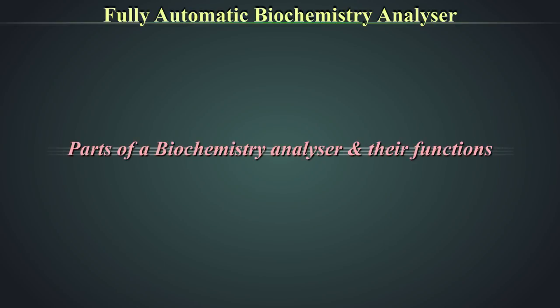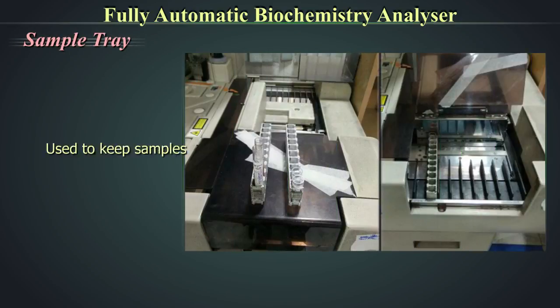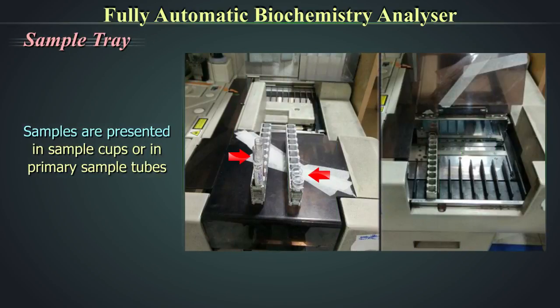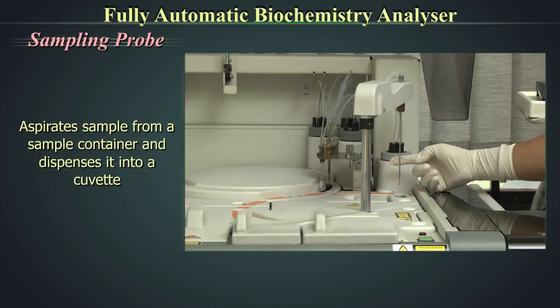Parts of a biochemistry analyzer and their functions: The sample tray is used to keep samples, which may be presented in sample cups or in primary sample tubes. The analyzer may have onboard barcode reading capacity or manual entry of sample ID. The sampling probe aspirates sample in conjunction with the sample syringe from a sample container and dispenses it into a cuvette.